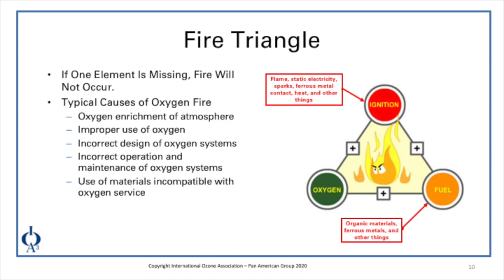Typical causes of oxygen fires include oxygen enrichment of the atmosphere, improper use of oxygen, incorrect design of oxygen systems, incorrect operation and maintenance of oxygen systems, or use of materials incompatible with oxygen service. In the design of oxygen systems, you want to minimize organic material in the vicinity of your oxygen storage tanks. Oftentimes you'll see concrete used near oxygen storage tanks rather than asphalt paving to avoid organic material in the vicinity. You will also see no smoking signs regularly posted around oxygen systems to try to eliminate ignition sources.